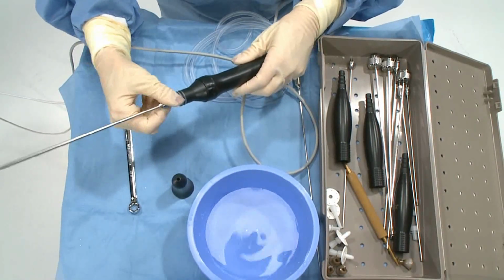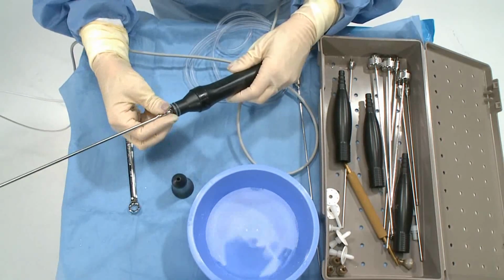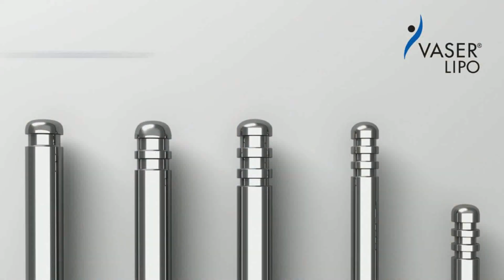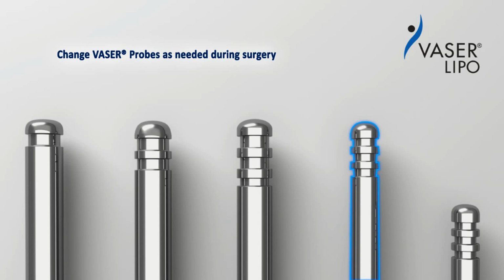Throughout the procedure, attach and detach Vaser probes as needed. In general, for a given diameter, probes with more grooves or rings fragment tissue more efficiently, but do not penetrate fibrous tissues as easily. For comparison purposes, a 3-ring 3.7 mm probe distributes approximately 70% of its energy from the sides and 30% from the front surface. A 2-ring 3.7 mm probe distributes approximately 50% of its energy from the sides and 50% from the front surface. A 1-ring 3.7 mm probe distributes approximately 30% of its energy from the sides and 70% from the front surface.